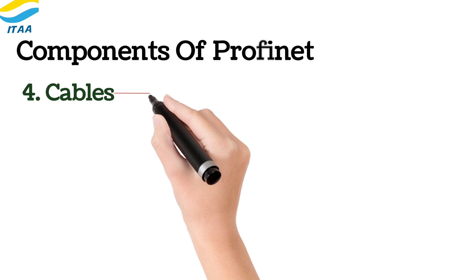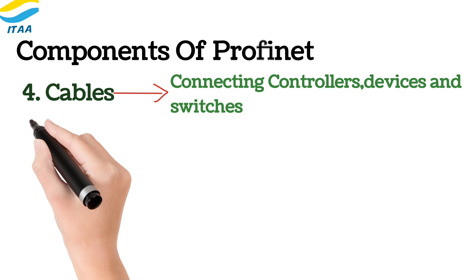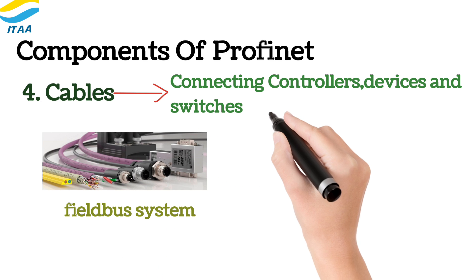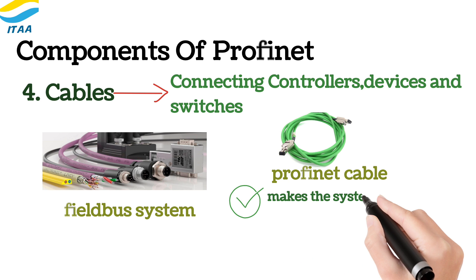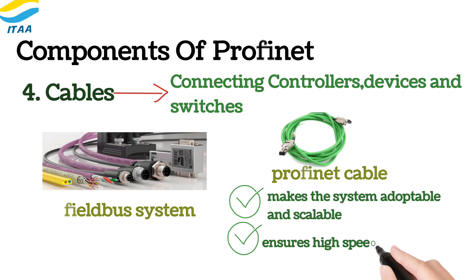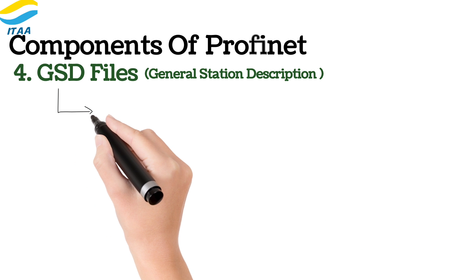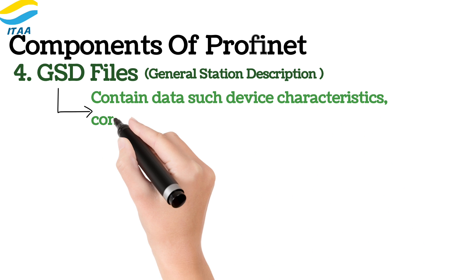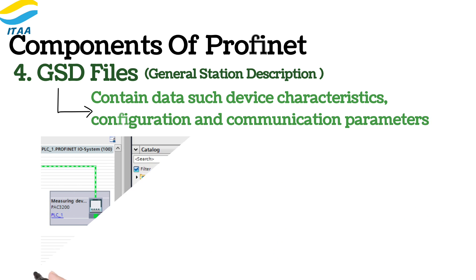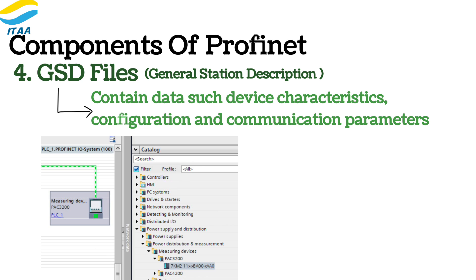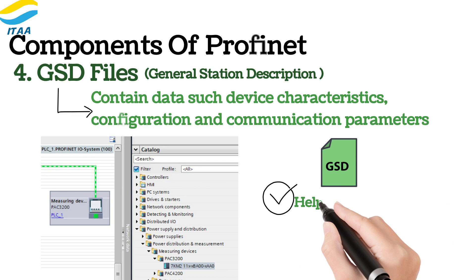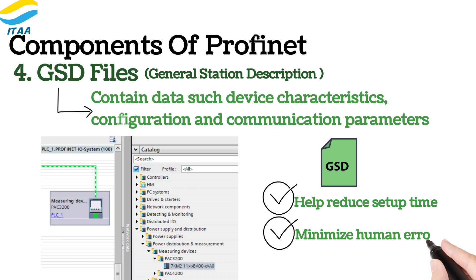Ethernet cables form the physical backbone of a PROFINET network, connecting controllers, devices, and switches. Unlike traditional fieldbus systems, PROFINET uses standard Ethernet cables, which makes the system highly adaptable and scalable. These cables ensure high-speed data transfer and are robust enough to endure the demanding environments of industrial settings such as extreme temperatures, vibrations, and electromagnetic interference. GSD files are like a blueprint for each device in a PROFINET network. They contain essential data such as device characteristics, configurations, and communication parameters. When integrating new devices into a network, these files make the process much simpler by providing pre-configured settings that allow the controller to recognize and communicate with the device immediately, helping reduce setup time and minimize human error during configuration.